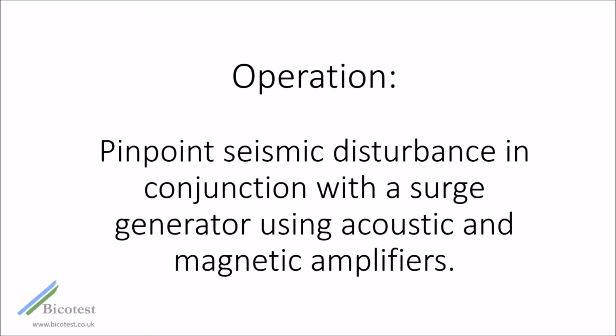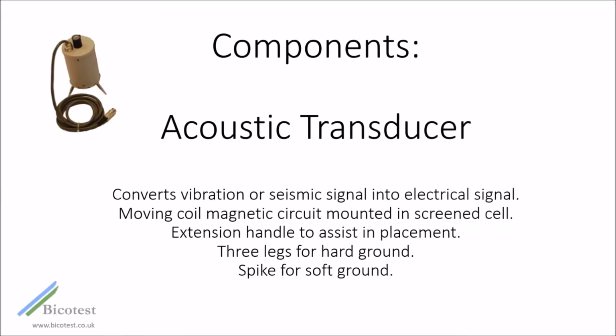In addition, the instrument incorporates a magnetic detector with separate amplifier to pick up and display on a separate meter the change in the magnetic field caused by each current impulse from the surge generator. This feature greatly assists in identifying the acoustic fault signal and differentiating it from the background noise. When an acoustic signal is indicated coincident with a visual signal from the magnetic detector, the position of maximum acoustic signal may then be determined to pinpoint the fault position.